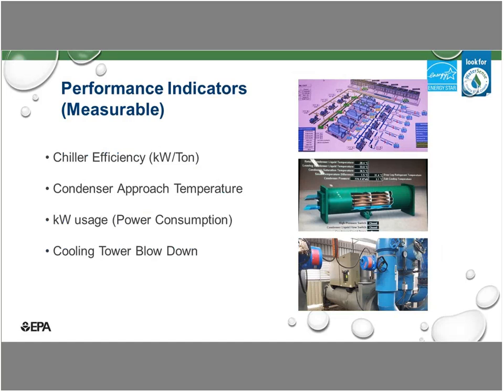The other numbers are the condenser approach temperature, which is your refrigerant temperature minus your water leaving temperature. Of course, if you don't have those things, we can always clamp your power line to look at your kilowatt usage to establish the baseline. For the water side, we put a meter at the blowdown, before and after. With your conventional chemical methods where you have your blowdown, we put a water meter there, and once we take a baseline, say over one, two or three months, we will take that meter and install it in our blowdown on our site so that you can track the differences in the blowdown volume.